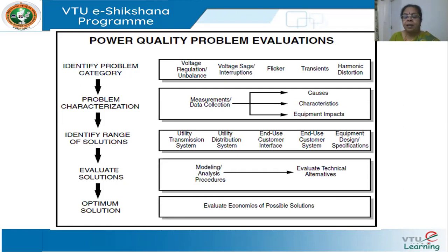For example, if you find that a consumer's meter is periodically failing, right? It could be because the utility has an overvoltage at that point, and the meter supply is derived from the utility by rectifying the utility voltage. So is it a problem coming like that from the utility side? Or is it just that they're using some substandard cheap digital meter available in the market? So you think of all the possible solutions.